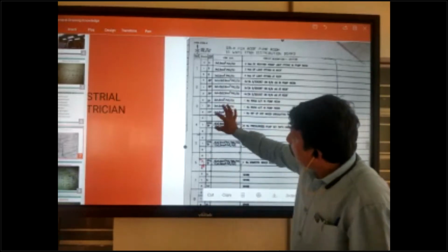If there is a star after it, this means ELCB or RCCB, and you can install either one here. And if the gap is like that, with only the center part written and TP written, you can install a triple pole MCB. Okay.